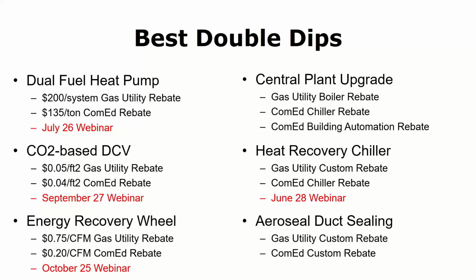If you put in an efficient chiller, you can get one that qualifies for one of the ComEd chiller rebates, and on the gas side, it's a custom rebate. It seems weird, why give a rebate on a chiller that doesn't even have a gas connection? The reason is we take the waste heat off the chiller, and instead of sending it to the cooling tower to dump outside, we send it back into the building for heating purposes, either reheat on the VAV boxes, preheating domestic water, heating a swimming pool, and basically offset the gas usage of the boiler. So the boiler won't have to run as much because we're using free waste heat found on the chiller to unload the boiler.